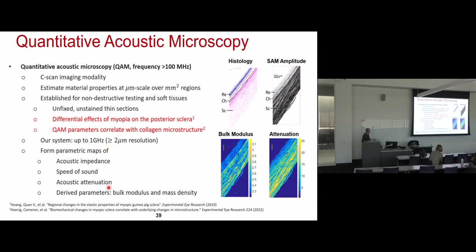And we, again, could use it in myopia, but I'm not going to be talking too much about this here. And so we have designed this instrumentation up to 1 gigahertz center frequency. So that's times 10 again. So it's 100 times greater than the baby picture again. And that gives you a resolution in the micrometer range. In fact, it probably should be a smaller-than-or-equal sign. So the resolution is smaller than 2 microns. And so we can make quantitative images of acoustic impedance, speed of sound, or acoustic attenuation, and some other parameters like the bulk modulus and the mass density, for example.